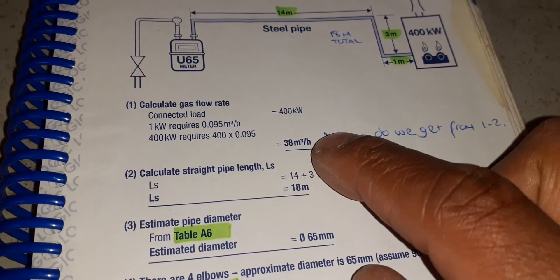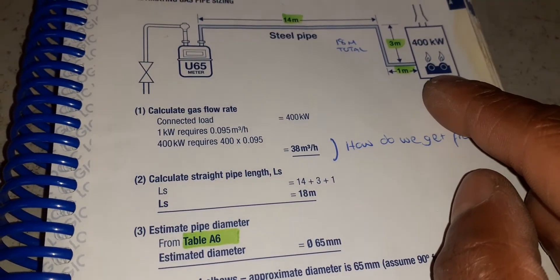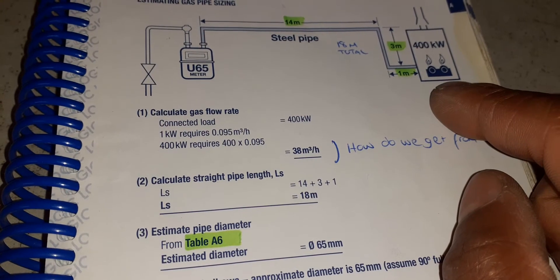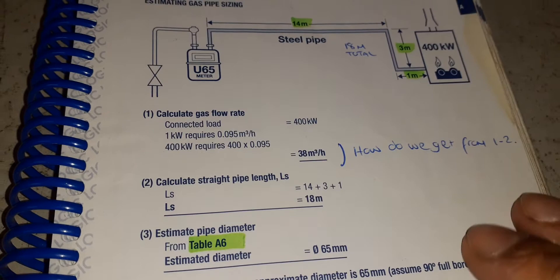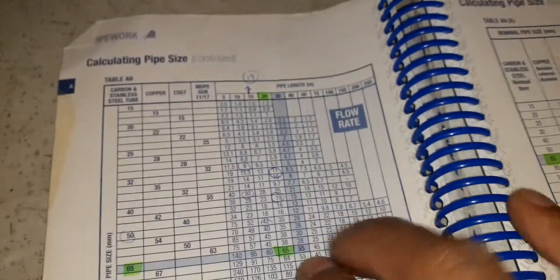So that will give us our flow rate that is required to provide a 400 kilowatt boiler with adequate gas. That will let us know the size of pipe we need depending on our pipe run. We turn over the page and it shows you here...